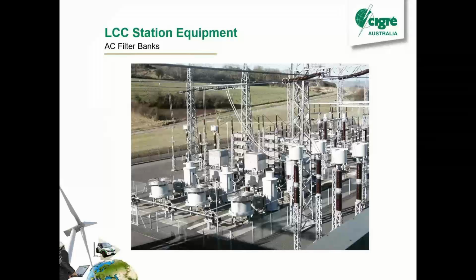Okay, so we'll just go through some photos. This is a picture of an AC filter bank. You can see it's made up of some reactors, some resistors stacked up, and some capacitor banks in the back. So you can have single order, double order, triple order. They're basically just combinations of RLC components with some surge arrestors and CTs in there. There's a big art with HVDC design, which is the AC filter design. There's all sorts of compromises you have to take into account. But yeah, you usually end up with a certain configuration.